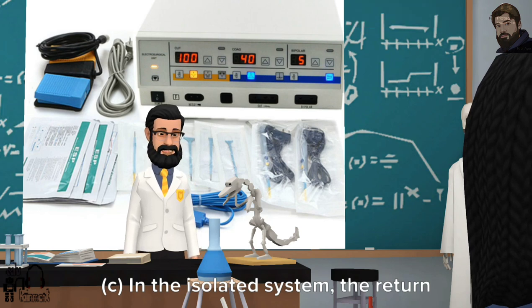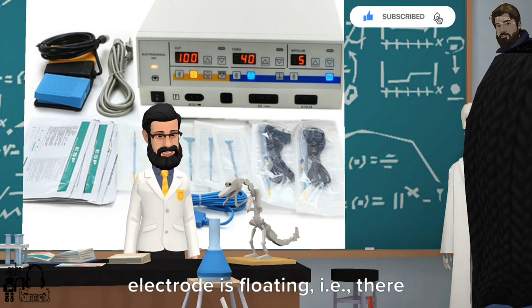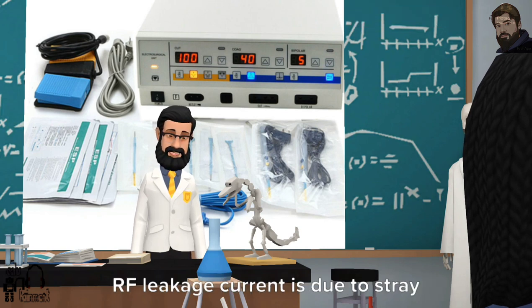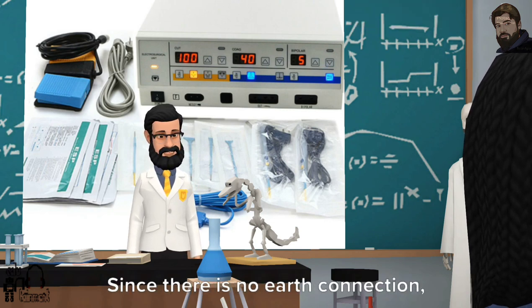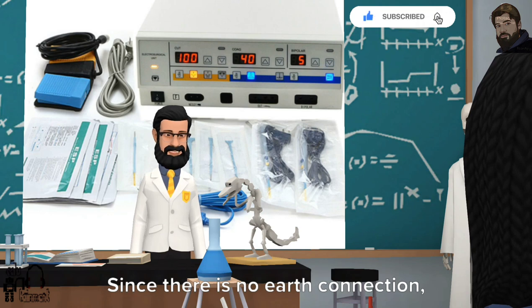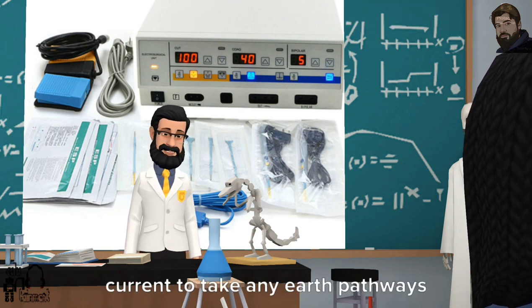In the isolated system, the return electrode is floating, that is, there is no intentional connection to earth. The RF leakage current is due to stray capacitance within the machine. Since there is no earth connection, there is no propensity for the RF current to take any earth pathways which may unintentionally develop. However, due to RF leakage pathways inherent in the equipment and leads, no machine can be considered as completely isolated.